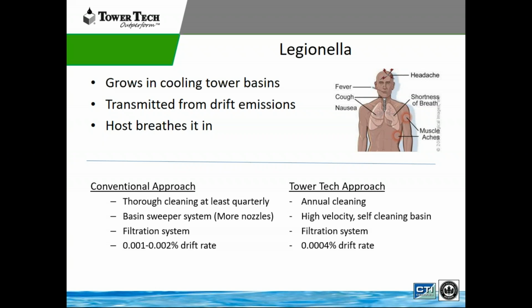There was one particular job that we sold where they were putting a tower in a parking lot, right by cars, and they didn't want the drift going on the cars. The reason Tower Tech was sold was because of its drift rate versus the traditional tower system. That was really the only reason, besides obviously the energy and water savings and everything else that goes along with it. Why do we have to be concerned about Legionella? Because ASHRAE Standard 188P says we have to. This is more of the building operator standpoint. When there's a standard, there could be some issues if you don't adhere to that standard when we talk about water.